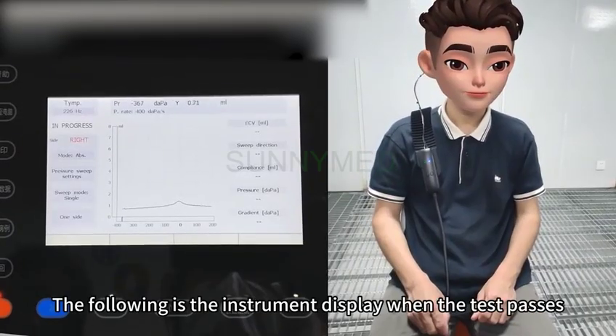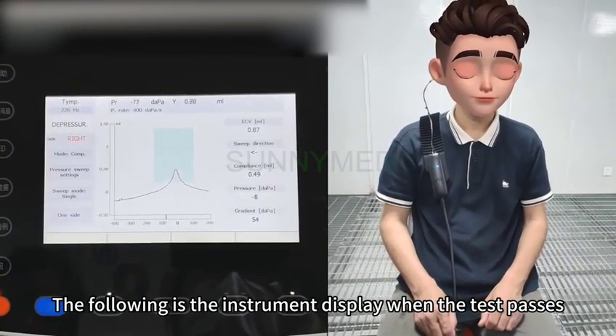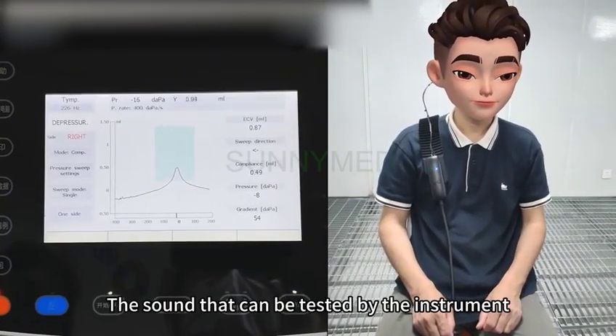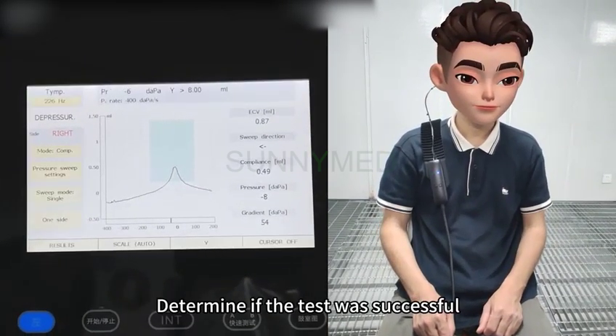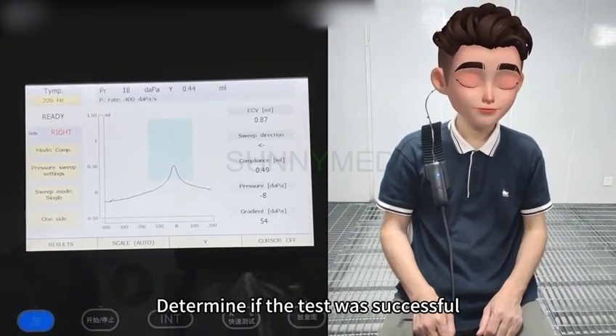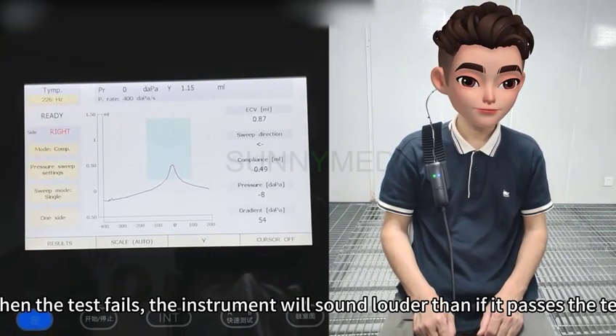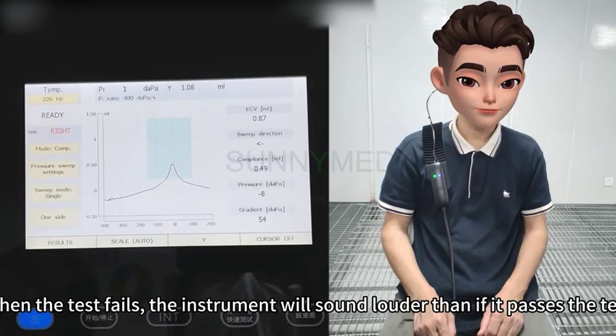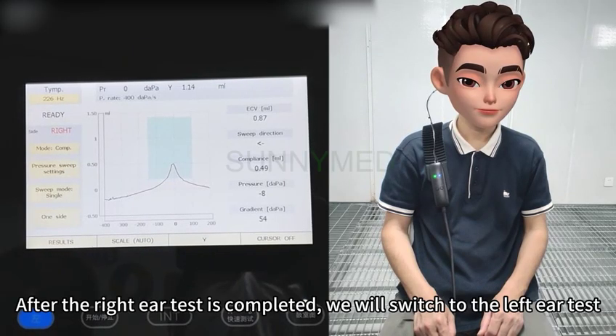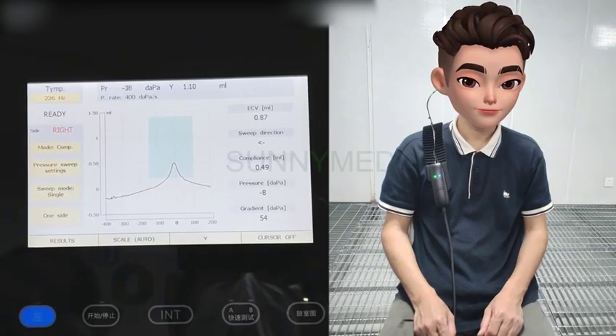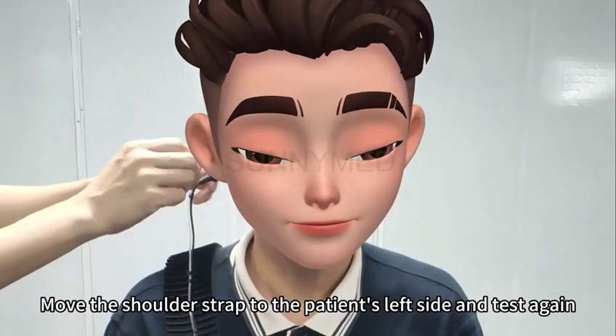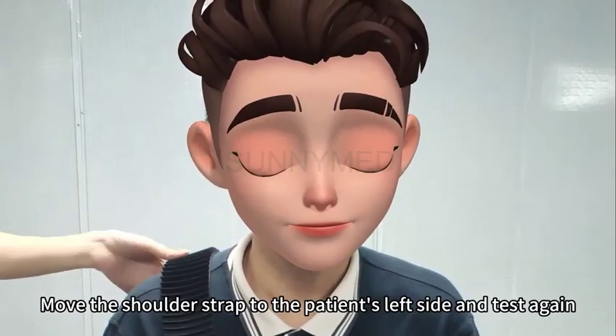The following is the instrument display when the test passes. The sound that can be tested by the instrument determines if the test was successful. When the test fails, the instrument will sound louder than if it passes the test. After the right ear test is completed, we will switch to the left ear test. Move the shoulder strap to the patient's left side and test again.